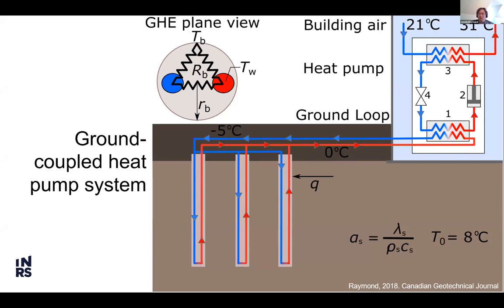Yeah, the system can be operated in both heating and cooling mode to ultimately provide energy savings. The performance of the system is highly dependent on the thermal properties of the ground, so the thermal conductivity shown by lambda and, to a lesser extent, the heat capacity. And the number of boreholes we have is often a function of the ground thermal conductivity and also the borehole thermal resistance, which we will discuss in more detail.